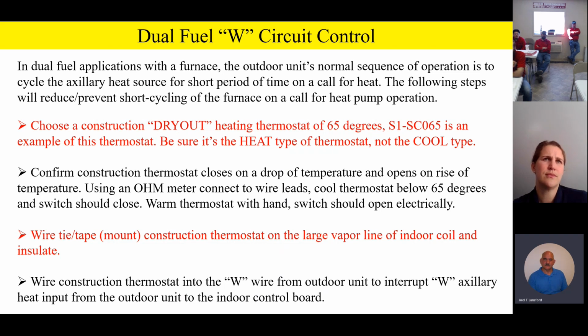And so when you take this outdoor unit that's designed to give you that W call every time you have a call for heat, for 1 minute, on a furnace, it can cause the furnace to short cycle. That's the long and short of it. So basically the furnace comes on, gets a W call, goes through its heating sequence. It takes about 30 seconds before the blower comes on. So now the thing runs for 15 or 20 seconds, then bang, it shuts the furnace off, right? And so you can short cycle the furnace. Now, we haven't had any reliability issues yet, but we don't want to have any reliability issues.